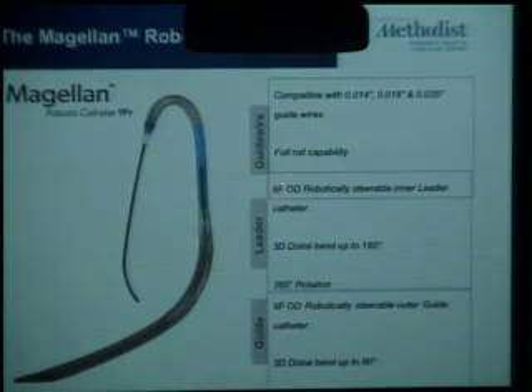Now, if we go over to the main system that I've been using, essentially the sheath is a 9 French outer diameter. That may not be much to the medical students, but I'd say it's on the relatively big side. What's important to us when we talk about French size is the ability to do everything percutaneously. Obviously, the larger the sheath, the less likely we are to do it percutaneously. Although we do obviously bend the indications a little bit, and we do use some percutaneous devices and closure devices to close the arteriotomies or the puncture sites. But nevertheless, it's on the verge of not being able to close it with the closure devices that exist on the market as far as the indications.